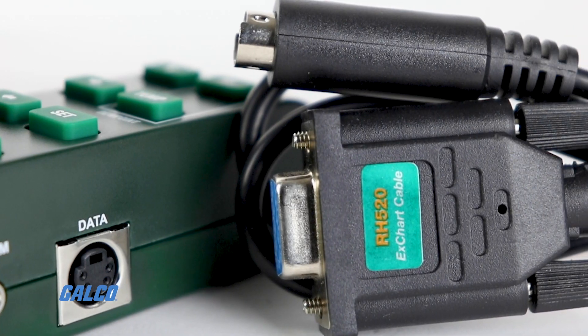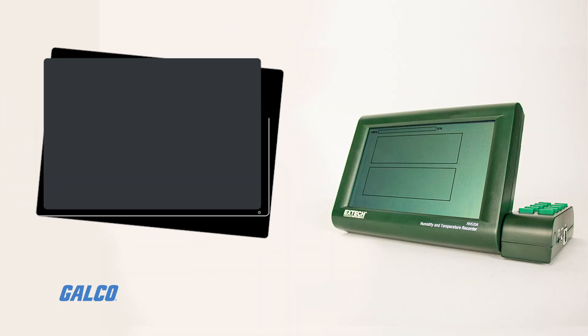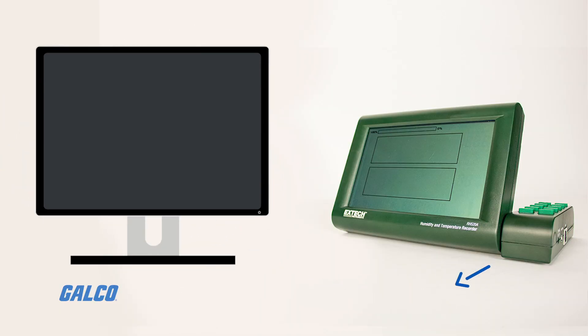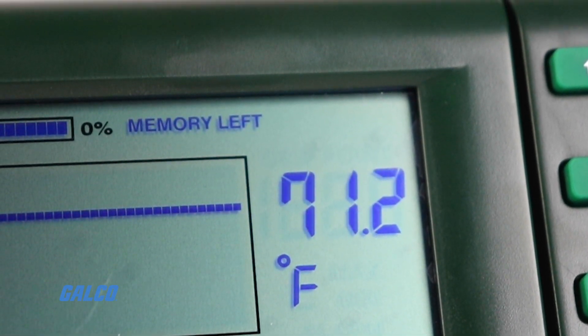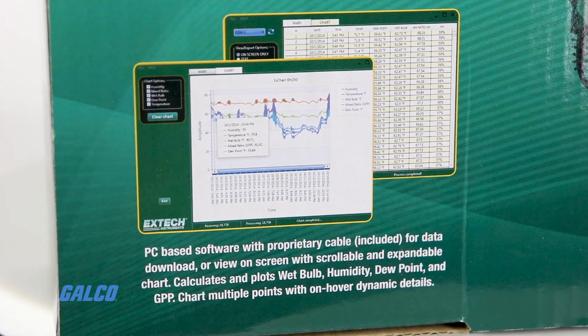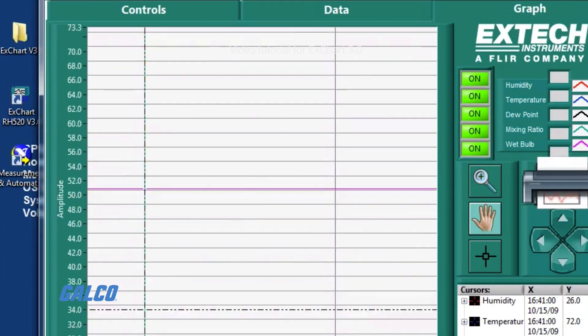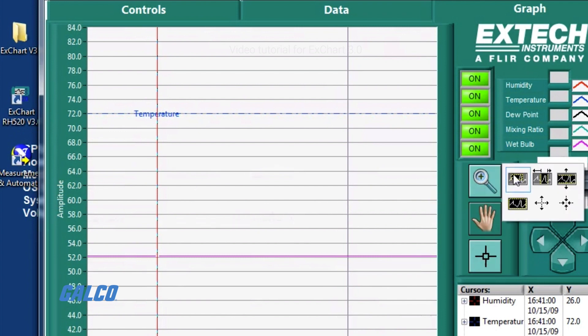An RS-232 serial port allows for data transfer between the chart recorder and a PC. The RH520A is able to calculate dew point on device, and the included Windows-compatible ExChart software is further able to calculate wet bulb and grains per pound based on data recorded by the chart recorder.